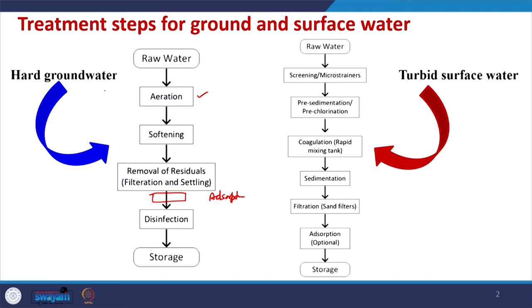If the water is surface water and it is turbid - which is highly possible during rainy season - it will contain a lot of sediments that have to be removed. First we screen the water to remove the maximum amount of suspended material. Then some pre-sedimentation and chlorination may be done to settle out most of the settleable solids. For removing dissolved solids and remaining suspended solids not getting settled easily, we use coagulation and flocculation methods, followed by sedimentation.